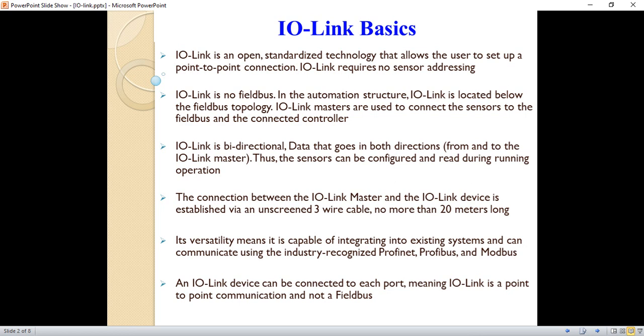Another characteristic is that the connection between the IO-Link master and the IO-Link device is established via unscreened three-wire cables, and the wire length must be less than 20 meters. It also has versatility, meaning it is capable of integrating into existing systems and can communicate using industry-recognized Profinet, Profibus, and Modbus communication protocols.